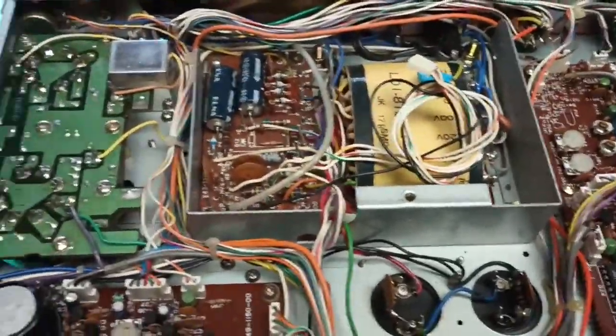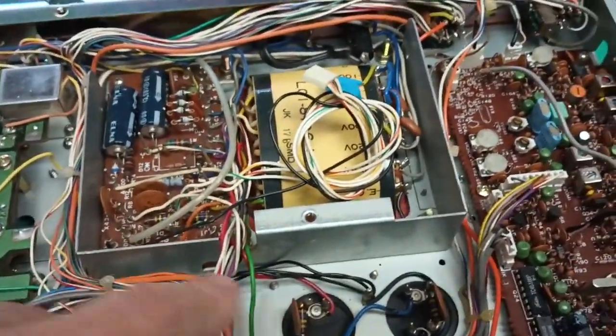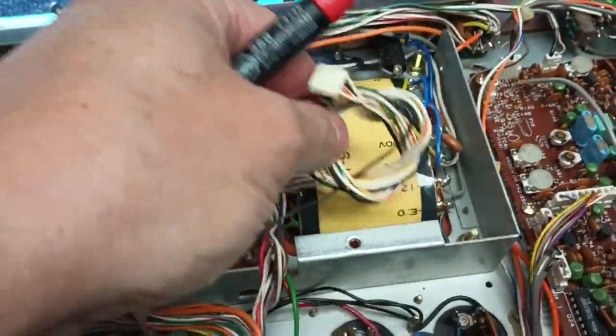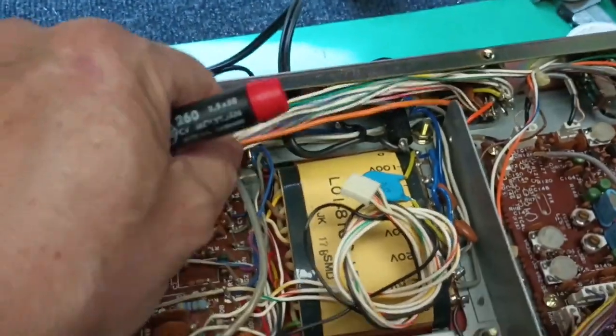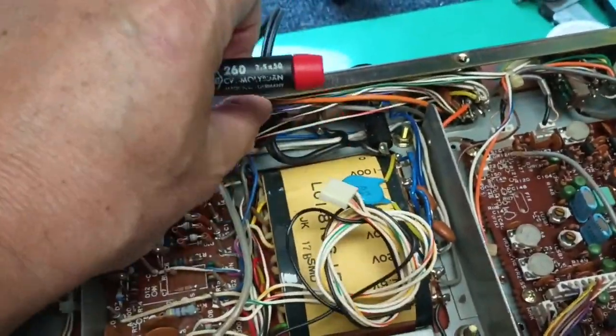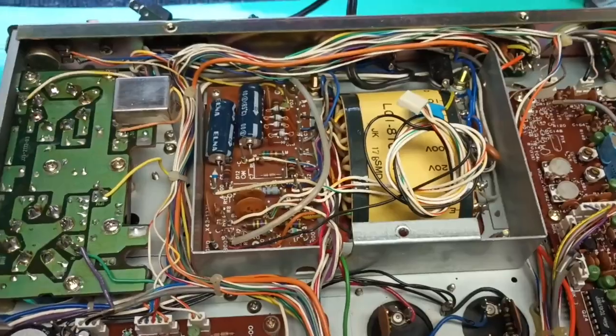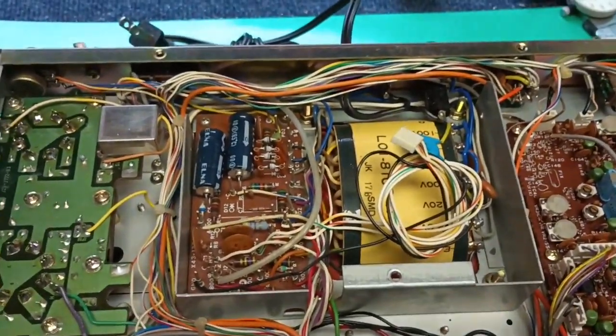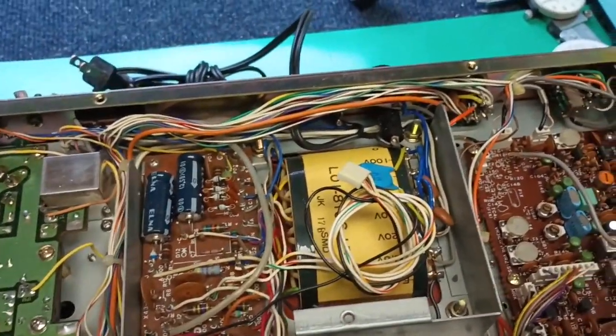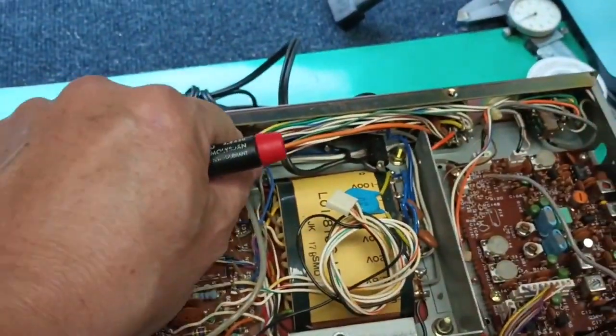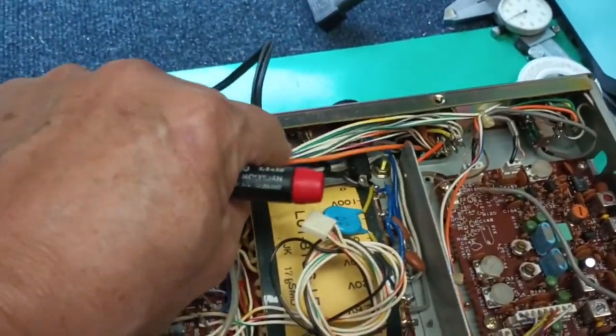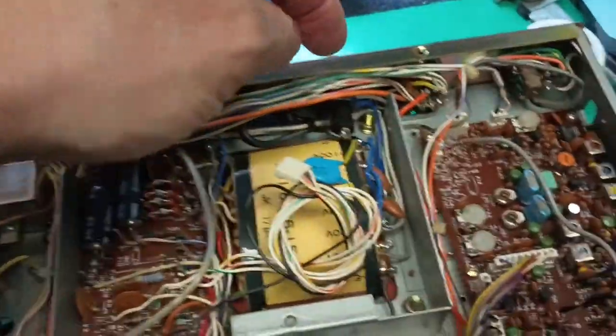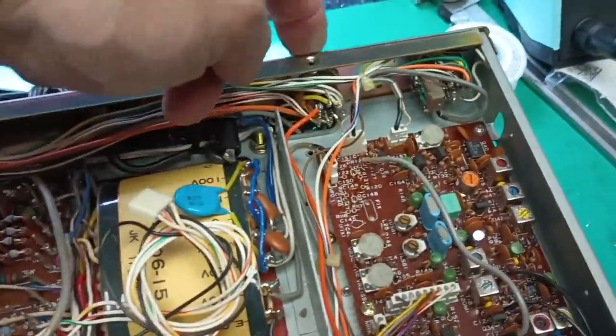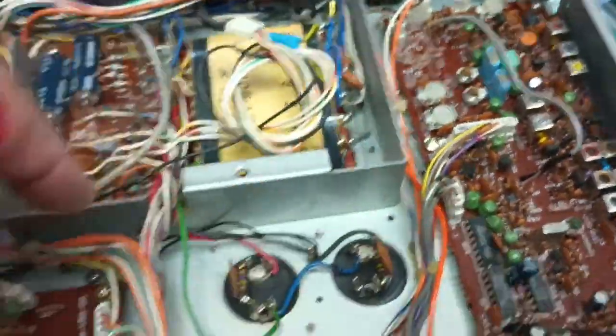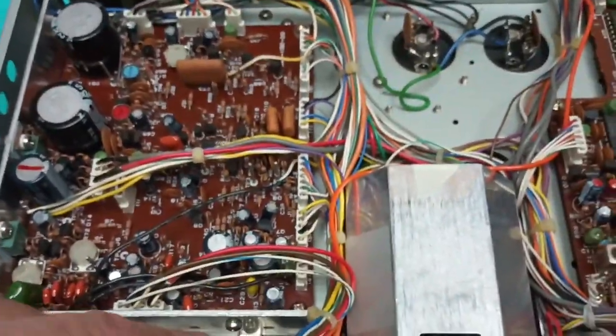So I need to clean all this wiring up. No excuse for this. These high voltages, several hundred volts, were strapped in tightly with this wiring back here. That's inexcusable. The standard is not, does it work, that we get away with it? The standard is, is it correct design? And the answer is no. We don't take several hundred volt wires and strap them in with all these low voltage signals. This wire to the remote socket went right through this high voltage area, so that was taken off and rerouted here to get it away from that.